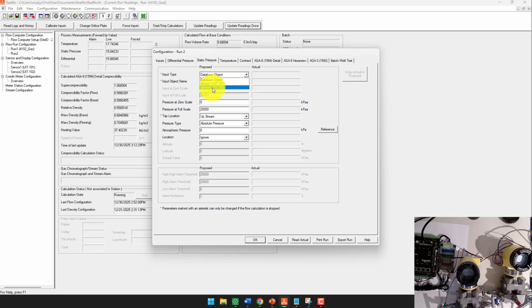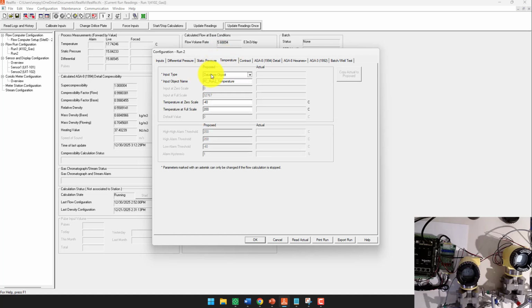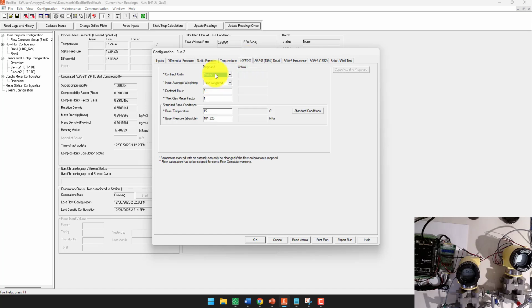Static pressure, same thing again. We're going to use sensor 2. Everything else looks good. Temperature, we will use sensor 2. The contract units will be metric 1. The contract hour will be 8 AM again, so we'll make sure that's set to 8. We want to make sure this is set to 15 and 101.325 if it's on metric 1. If this ever gets changed, you can just go here and hit standard conditions and it'll reset it back for you. So make sure those are both set, but you could cheat by just pressing this.